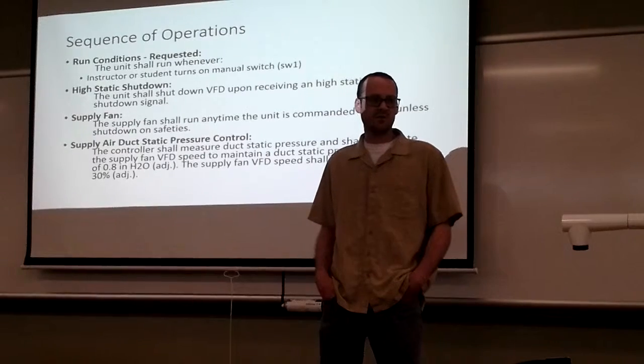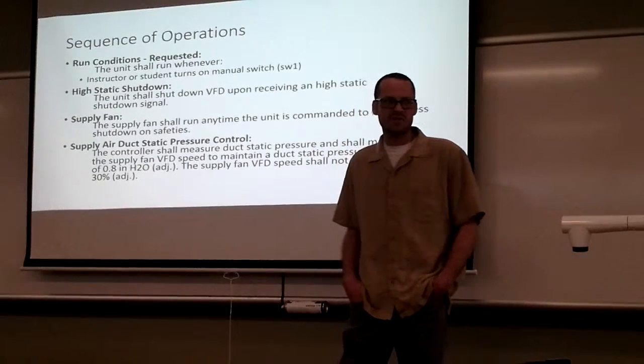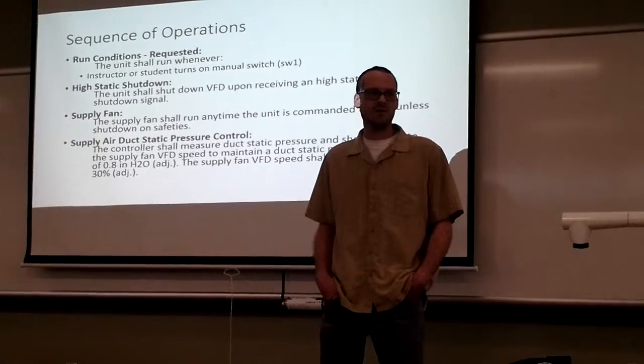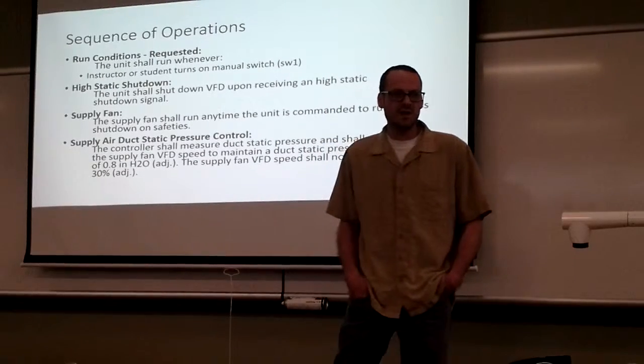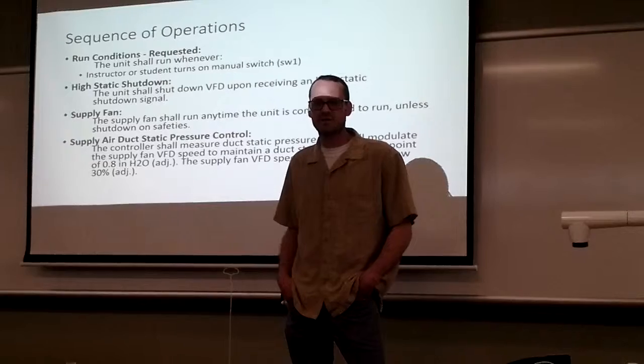The supply fan shall not drop below 30%. Another safety is a high static shutdown and if the VFD receives a signal that it's too high it will shut the fan off. And the supply fan will run anytime the unit is commanded to unless shut down on safeties.